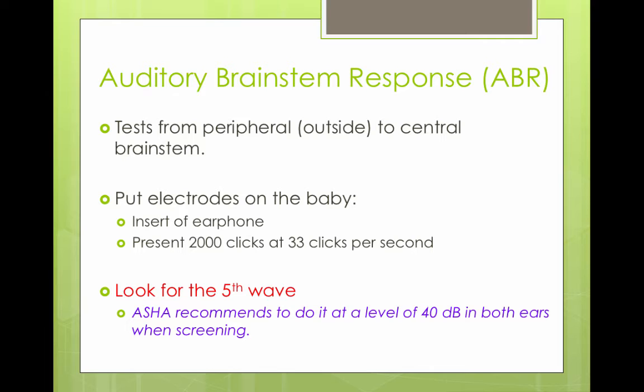Electrodes are put on the baby — this does not hurt the baby at all. Insert earphones are put in the child's ear canal. There are 2,000 clicks at 33 clicks per second, so you hear click, click, click, click, click...